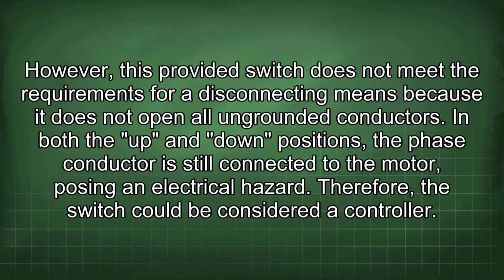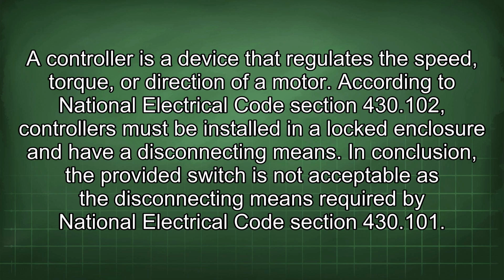However, this provided switch does not meet the requirements for a disconnecting means because it does not open all ungrounded conductors. In both the up and down positions, the phase conductor is still connected to the motor, posing an electrical hazard. Therefore, the switch could be considered a controller. A controller is a device that regulates the speed, torque, or direction of a motor.